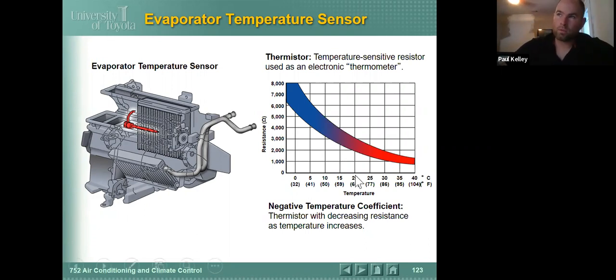So what it was reading was like 36, that was 6,000 ohms. The problem was it was reading 6,000 ohms when the actual temperature was more like 60. So the sensor was skewed, it was inaccurate. So what do you think the fix is?